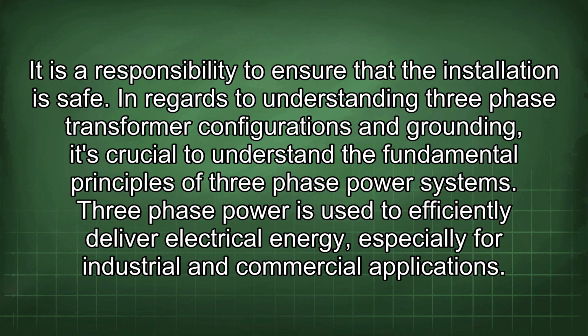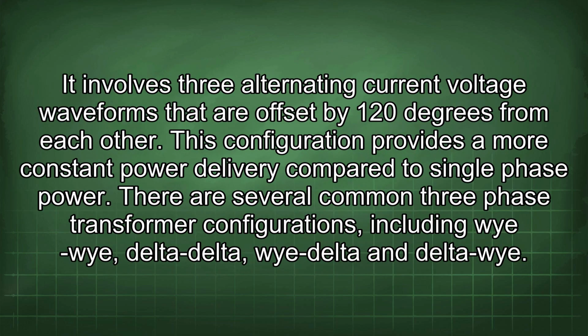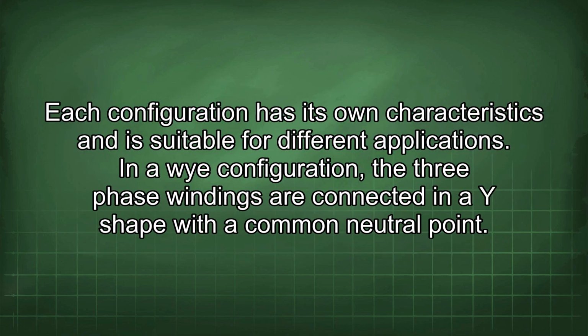In regards to understanding three-phase transformer configurations and grounding, it's crucial to understand the fundamental principles of three-phase power systems. Three-phase power is used to efficiently deliver electrical energy, especially for industrial and commercial applications. It involves three alternating current voltage waveforms that are offset by 120 degrees from each other. This configuration provides a more constant power delivery compared to single-phase power. There are several common three-phase transformer configurations, including YY, Delta-Delta, Y-Delta and Delta-Y. Each configuration has its own characteristics and is suitable for different applications.